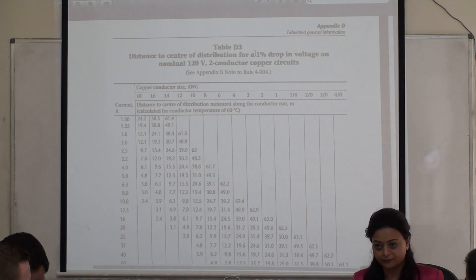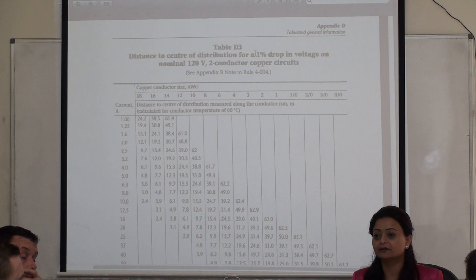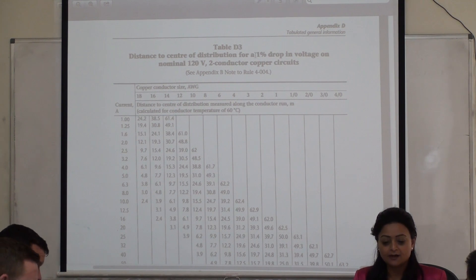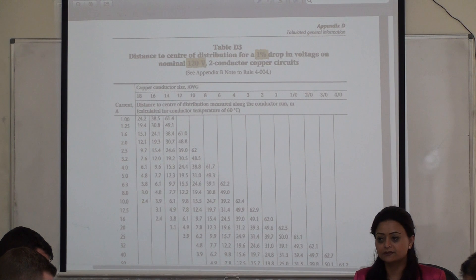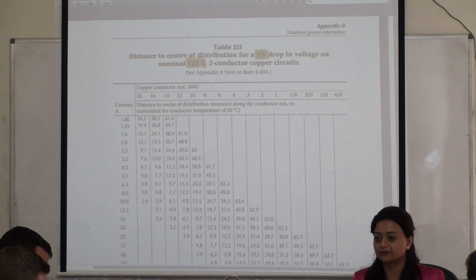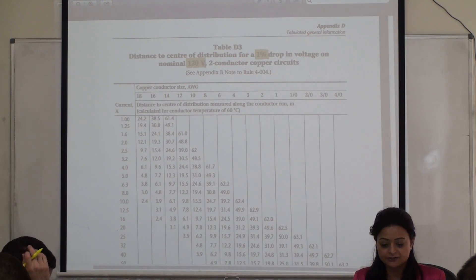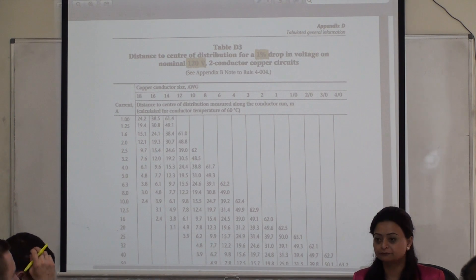I just threw some information at you. For that kind of question, you're going to come here to find your answers. This table is designed for 1% drop and 120 volts only. If I'm given 240 volts, 480 volts, or 600 volts, we're going to make more calculations than just reading the chart. If I'm given 2%, 3%, 4%, or up to 5% drop, I have to make more calculations than finding the answers just from here.